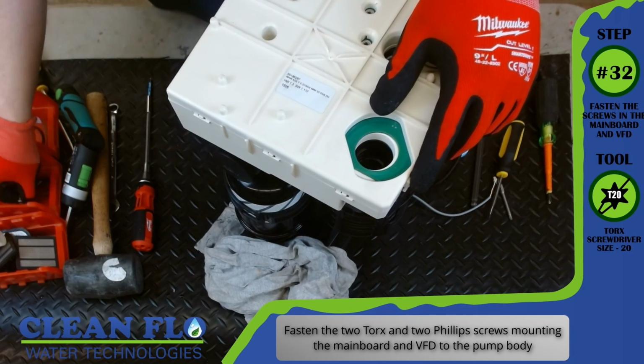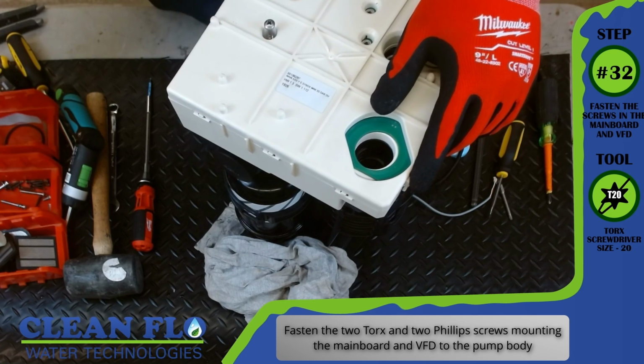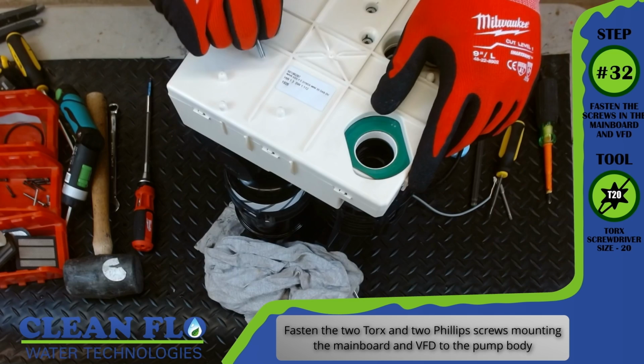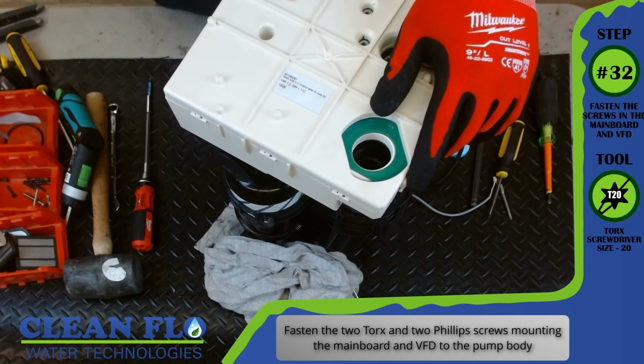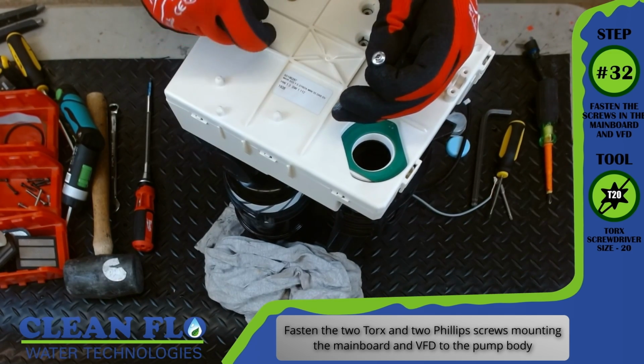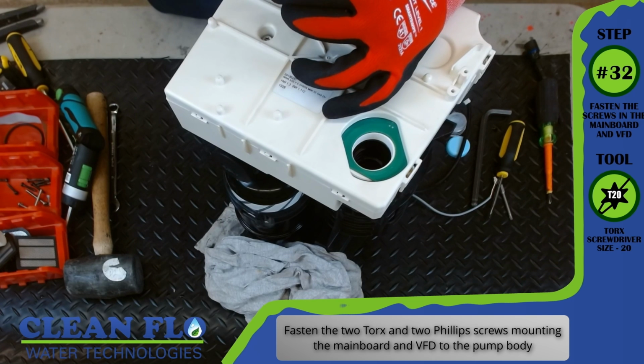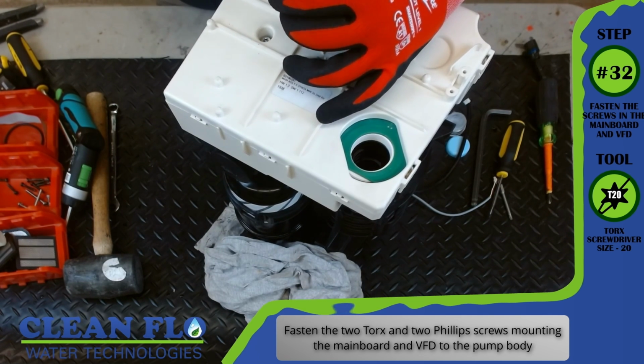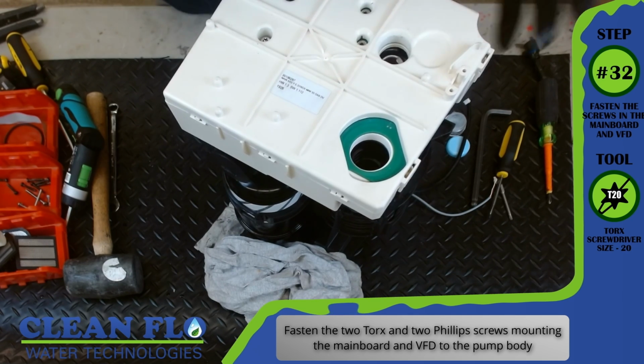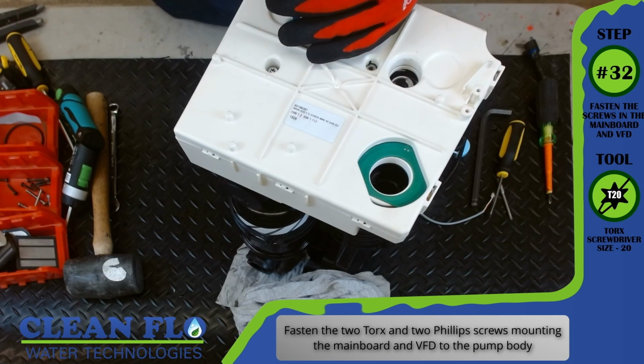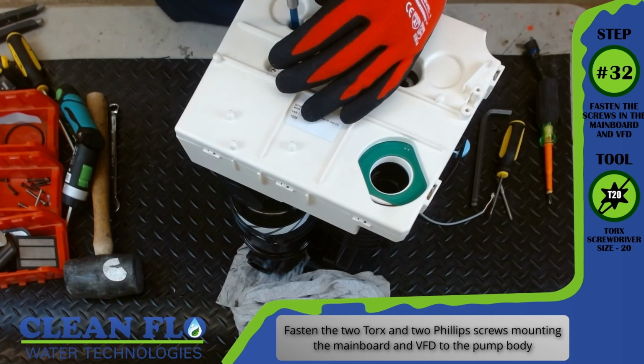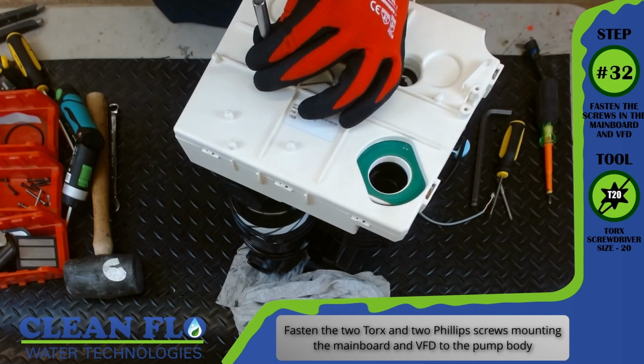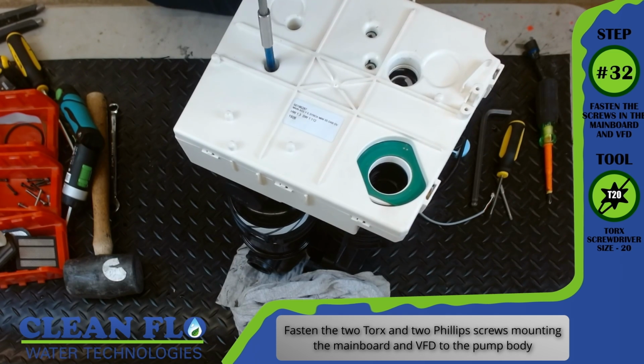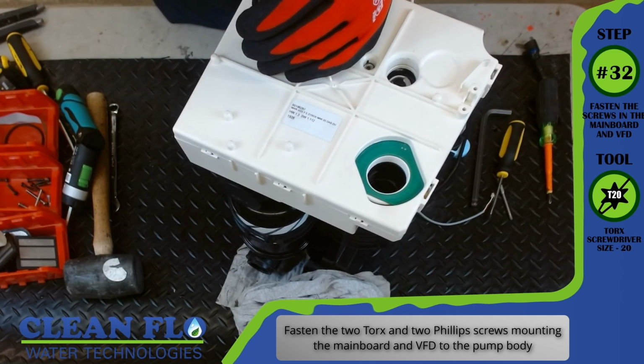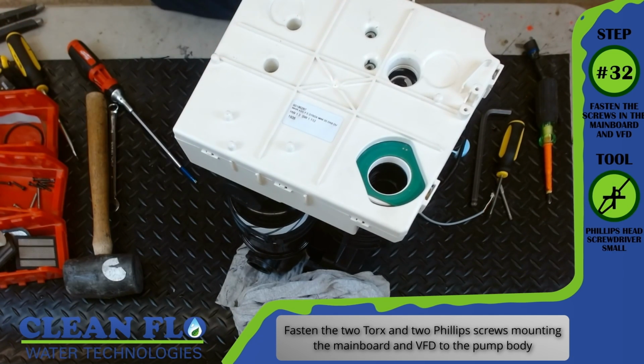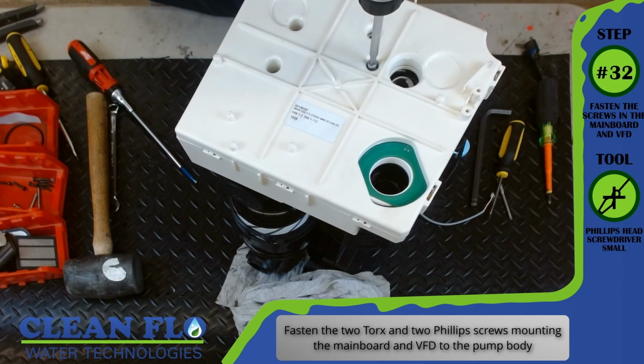Step number 32, fasten the screws in the main board and the VFD. Tool, T20 Torx screwdriver. Fasten the 2 Torx screws and the 2 Phillips screws mounting the main board and the VFD to the pump body. The 2 Torx screws actually structurally connect the main board and VFD to the pump body. The 2 smaller Phillips screws actually provide grounding from the circuit board to the motor assembly.